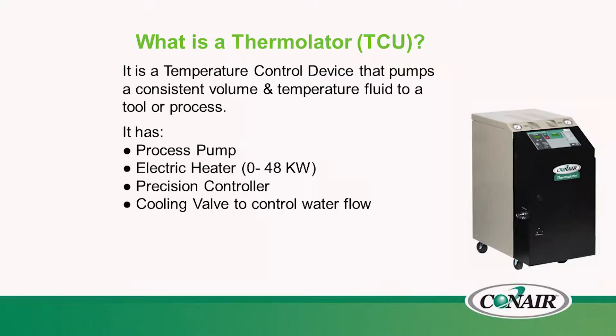What is a temperature controller or TCU? The temperature controller is basically a temperature controlling device that has a bulk pump that will move a volume of tempered fluid through a tool or a process. It requires a process pump, electric heater, precision controller, and a cooling valve to control water flow. The term Thermolator is actually a product trademarked by Conair back in the early 60s, and the Thermolator or TCU has been a workhorse in the injection molding industry.